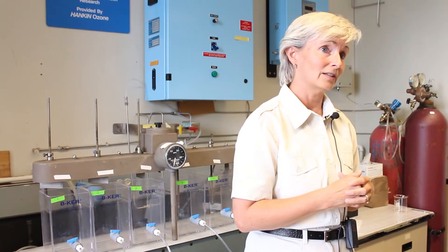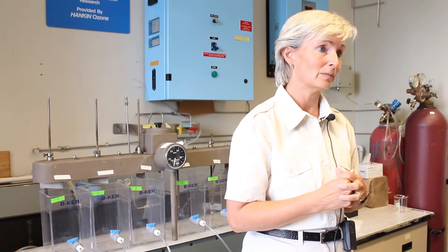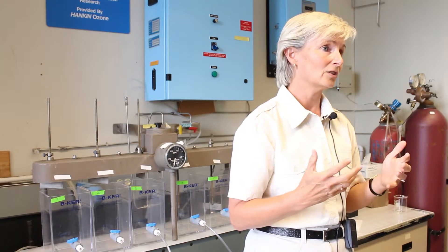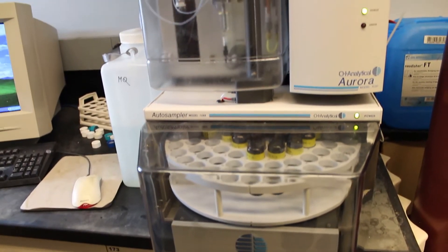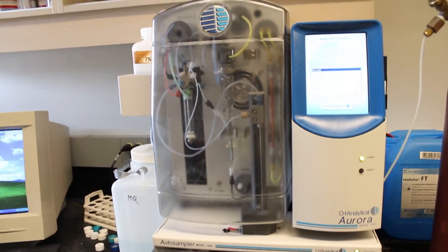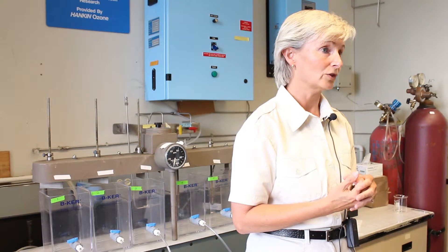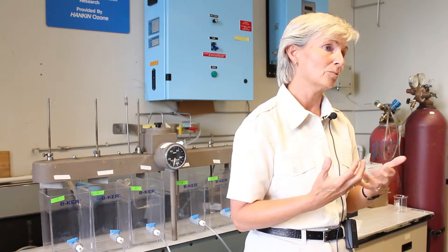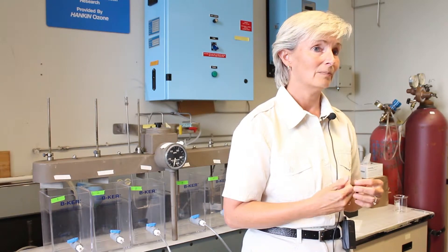On the other side of the coin, we have similar types of processes at very large scale with millions of liters of gallons being treated per day, where we might have large UV generating light systems which will irradiate light in a reactor in a water treatment plant. And if we add hydrogen peroxide to that reactor along with the UV light, we get the same kinds of hydroxyl radicals. It's a much easier system to scale up.